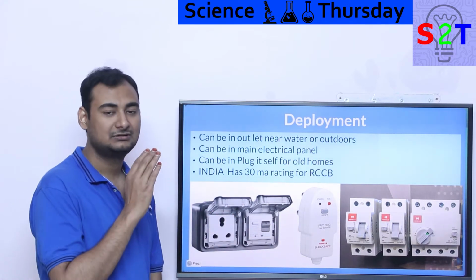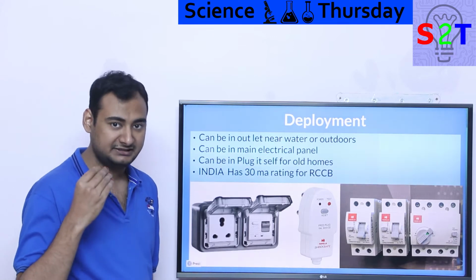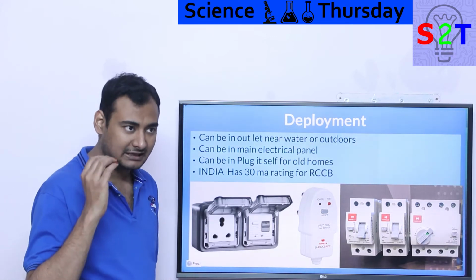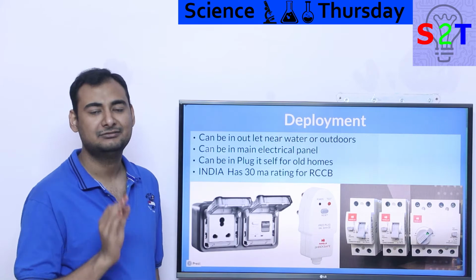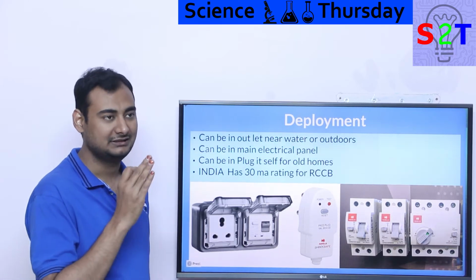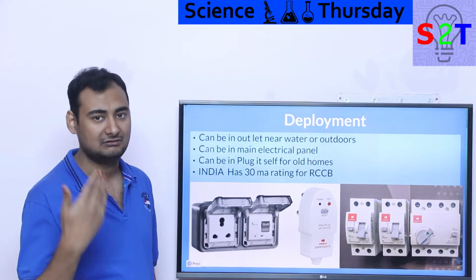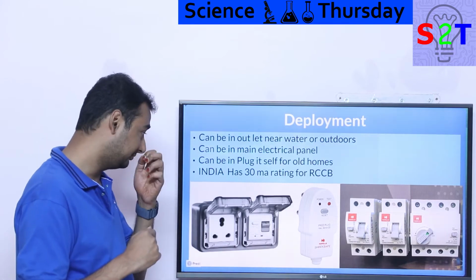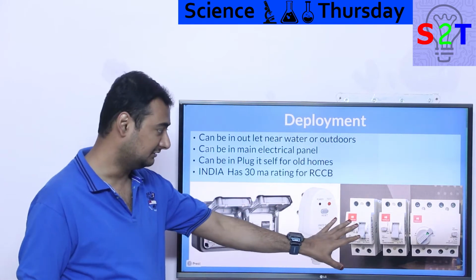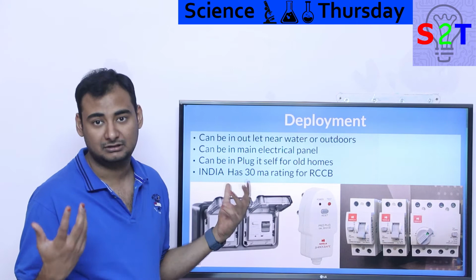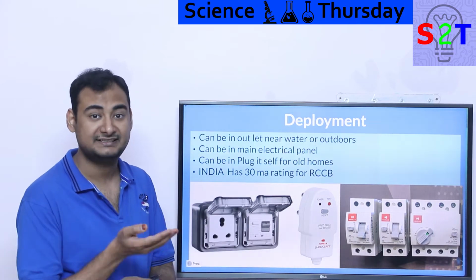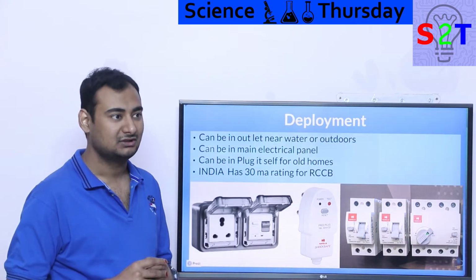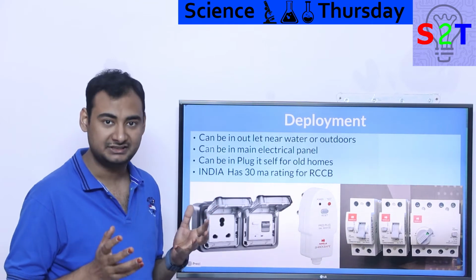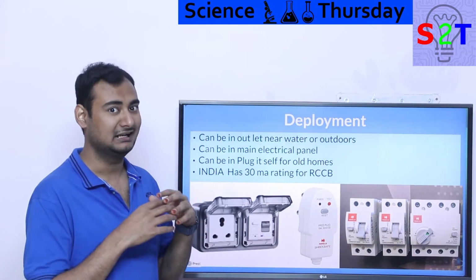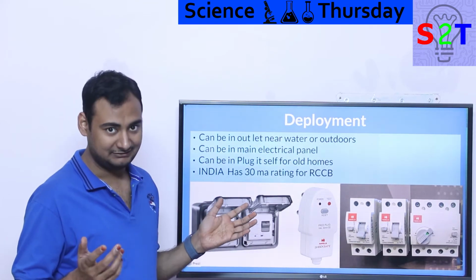That depends on basically the appliance designer. If they designed it competently enough, even close to competently enough, that should never happen. In a fault scenario, your fault current should always go to earthing rather than to neutral. So that is done. Now, what if you are living in an old house, or you bought a new appliance that requires GFCI because you are not very comfortable, let's say, for example, water geysers, they have water and a large amount of electricity. So what do you do then?